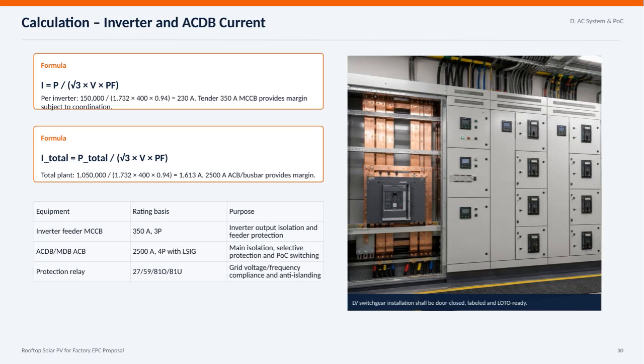Here we focus on calculating the inverter and ACDB current for the rooftop solar PV system designed for the factory EPC proposal. The key current formula is I equals power divided by the square root of 3 times voltage times power factor. For each inverter rated at 150,000 watts, using 400 volts and a power factor of 0.94, the current calculates to 230 amps. To ensure reliability and coordination, a 350 amp MCCB is specified, providing a safety margin.